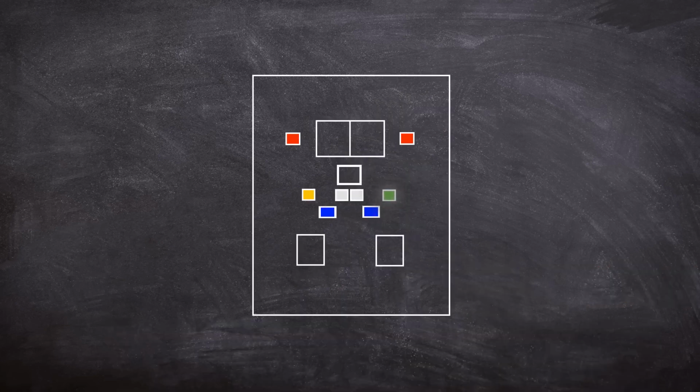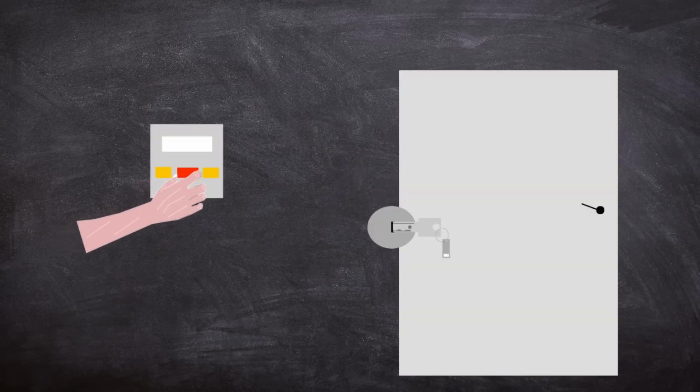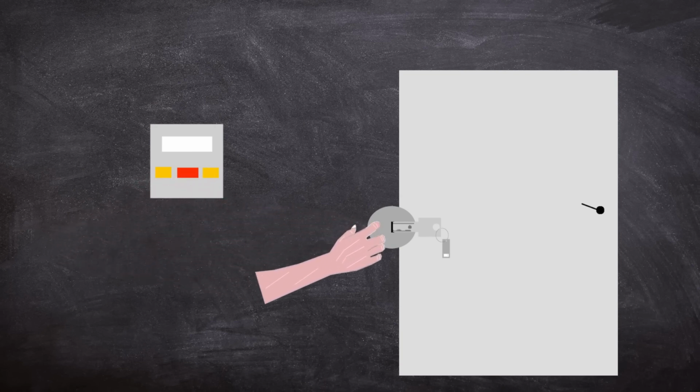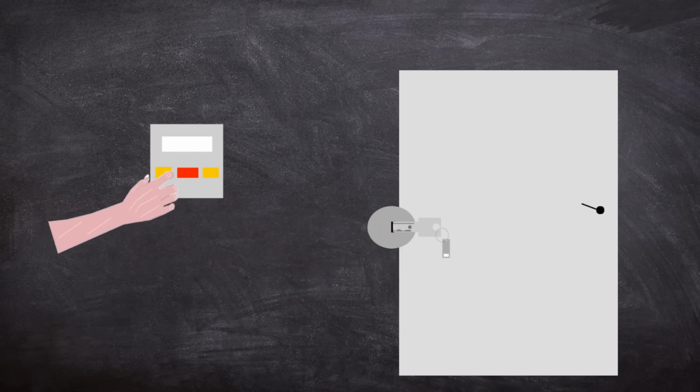To gain access to the room, the operator now performed the other non-standard procedure, which, ever since the monitor probe had been removed a few years before, meant that access to the irradiation room was achieved by rapidly cycling the buttons on the radiation monitor panel while turning the key in the door switch.